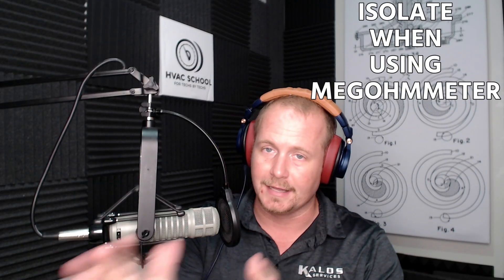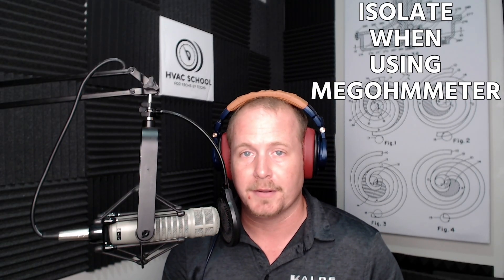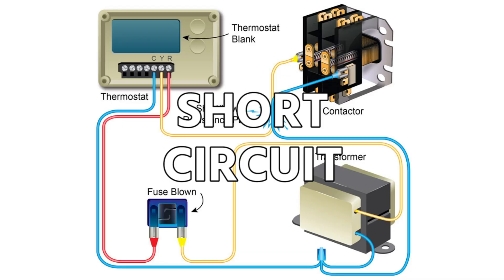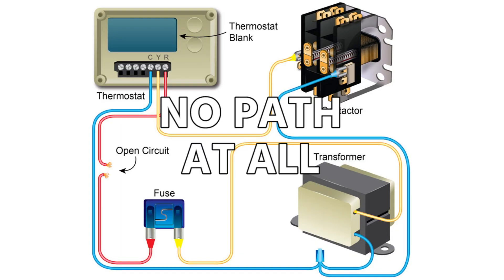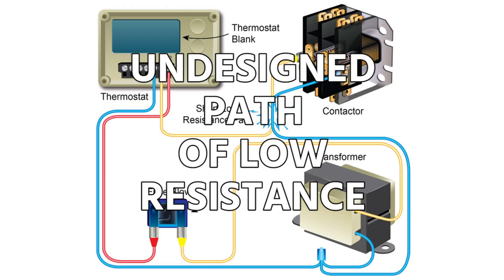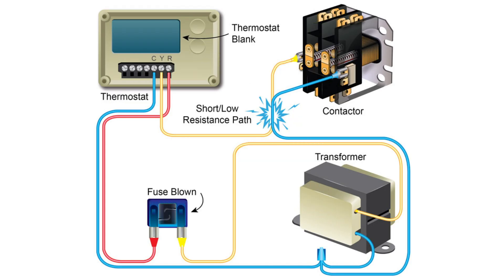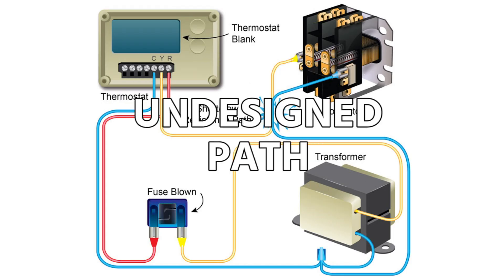You have to make sure that you're isolating when you're using a megohm meter. All that's doing differently than your regular multimeter on the ohm scale is increasing that voltage, which is going to help you find problems a little bit more accurately. The main thing I wanted to talk about here today is the difference between a short circuit — which is an undesigned path of low resistance — and an open circuit — which is no path at all. Open circuit: no path at all. Short circuit: undesigned path of low resistance. And maybe you can even just say an undesigned path in general.